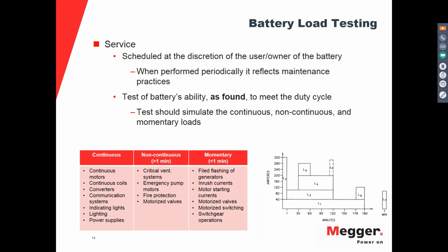And the table next to it shows the different loads that we would have to consider, and the battery is supposed to be able to meet those requirements. Whenever you have a permanent continuous load, it should be able to supply it. And whenever non-continuous or momentary loads are required from the battery, it should supply them. And that's what you're trying to achieve with that test.